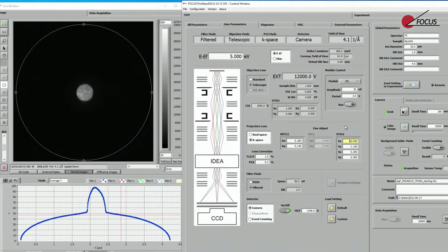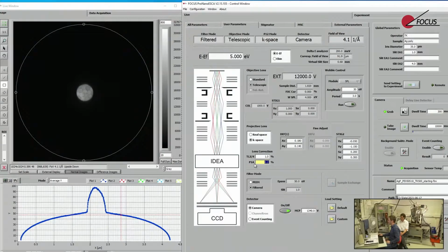And then one would have to check for astigmatism, the second stigmator, and for focusing with P1A. I did this already. Okay, so up to now, we have optimized our objective and the projectives with respect to the specific parameter settings, so the deflectors and some focusing we changed, but we have not optimized for the sample. However, it's the best starting point you can have for the k-space. If you've optimized the contrast aperture here, you will only have to make very small adjustments when looking at the real sample and when going to higher energies. Okay, so let's open the contrast aperture.